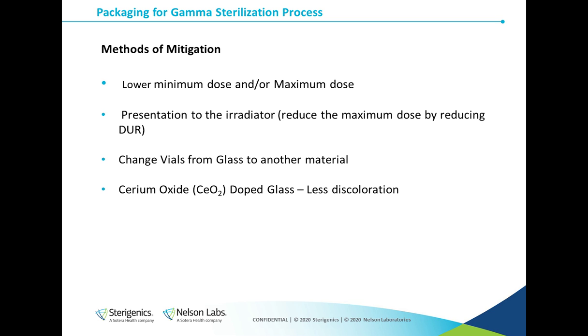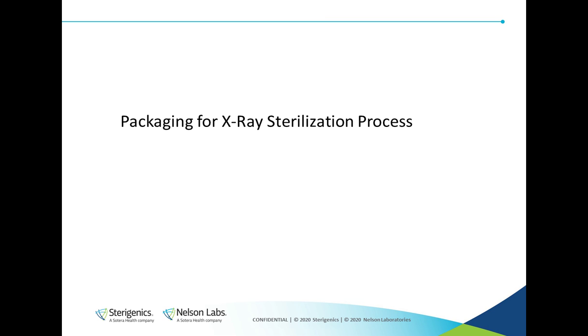That may not be enough to reduce the discoloration in this case, and we may need to consider using a different primary package, something other than glass. However, we could also look at purchasing glass vials that are doped with cerium oxide, for instance, which will reduce the discoloration from the irradiation process.